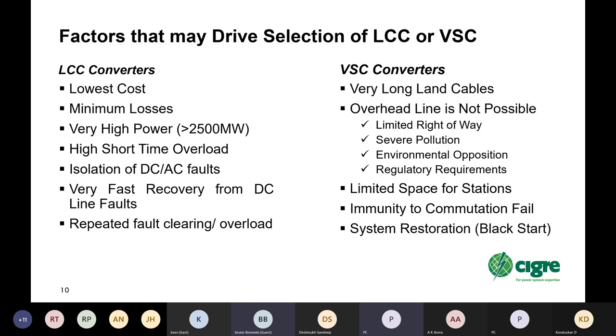Factors that might drive the selection of LCC or VSC. Looking at LCC converters first on the left, LCC converters have the lowest cost. If you're looking at equal power transmission capability, they're significantly cheaper, especially if you have a power breakpoint where it becomes necessary to add perhaps a second VSC converter to get the same rating, then the cost difference can be quite significant.